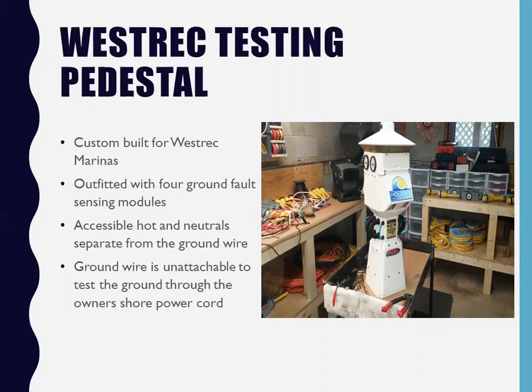Well, the problem is, just like you said, some guy in some old houseboat comes in, or some old powerboat that's got a residential panel, and he plugs in and goes into town and comes back and everything in the fridge is now the problem. Exactly right. Because he doesn't realize that he's had this minor leak for decades that, in a regular marina pedestal, you're never going to trip the breaker. I have pictures.